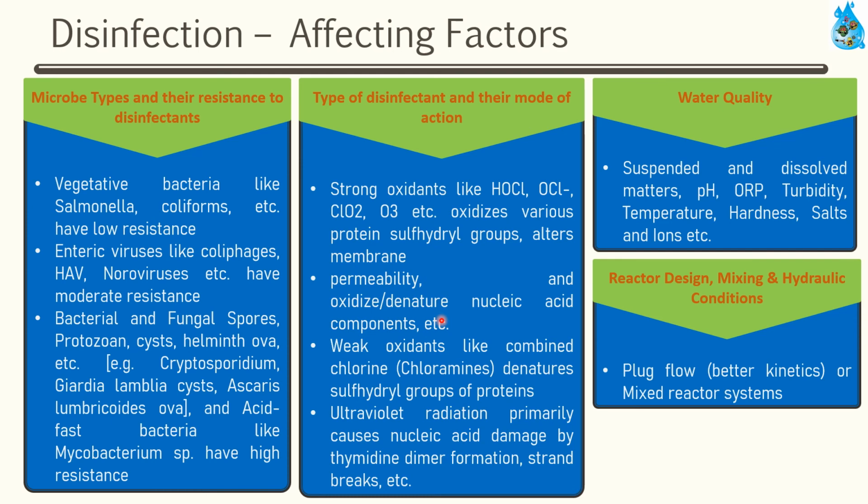The last parameter is reactor design and its mixing and hydraulic conditions. Reactors are nothing but the vessel in which you are going to perform the process of disinfection, and how this vessel responds to the chemical reaction also matters. So in the majority of conditions, plug flow type or mixed reactor systems are recommended for proper mixing, to achieve the maximum efficiency of disinfection.